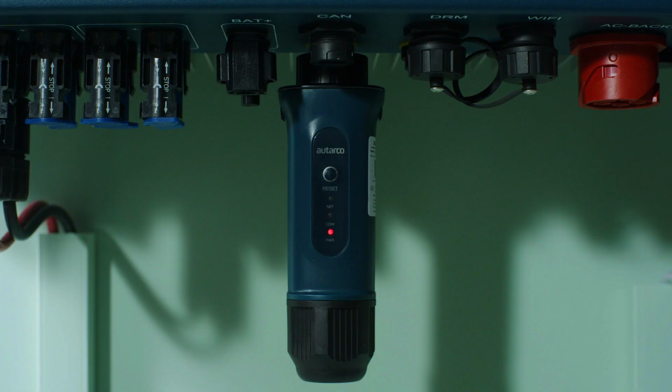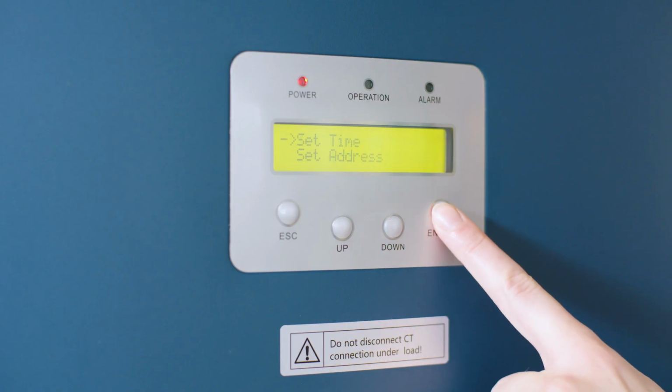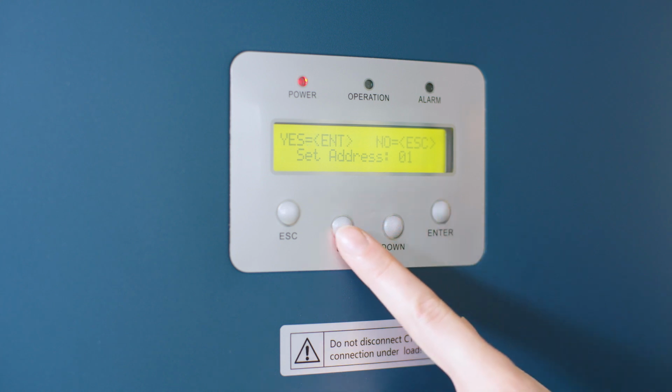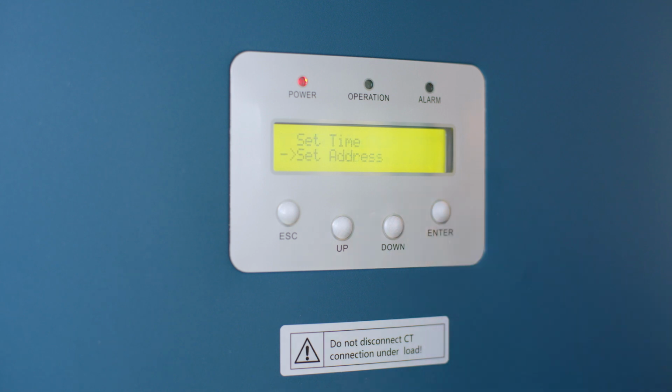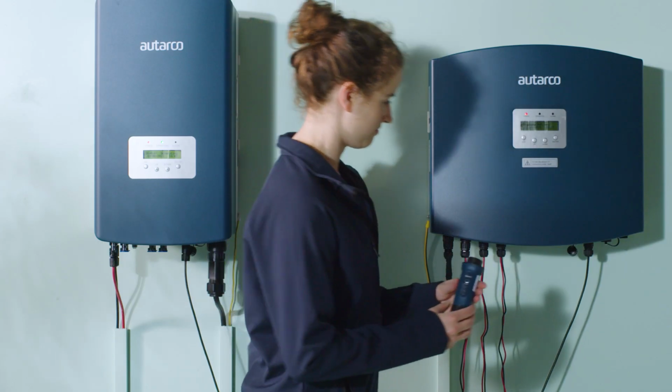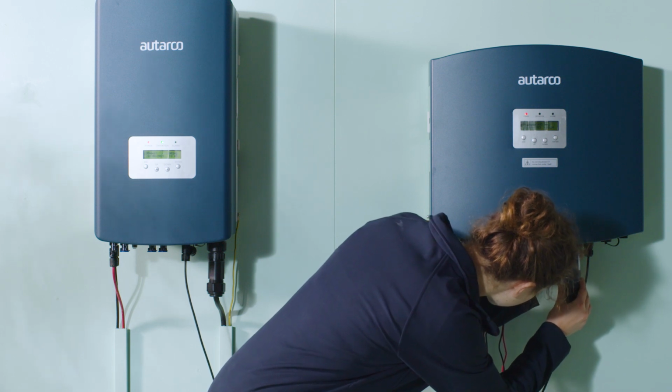The red power light is on, but the orange communication light is off. Your LAN stick is powered on, but not receiving data from the inverter, or of one of the inverters, if multiple inverters are daisy-chained. Check the address setting of the inverter. If the LAN stick is connected to only one inverter, the address setting of the inverter must always be 1. If multiple inverters are installed in a daisy chain, the first inverter in the line must be set to 1, the next to 2, and so on. If the numbers are not followed up correctly, the system's communication won't work properly.